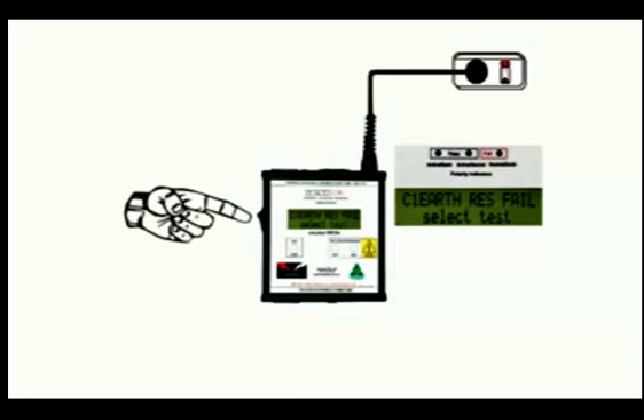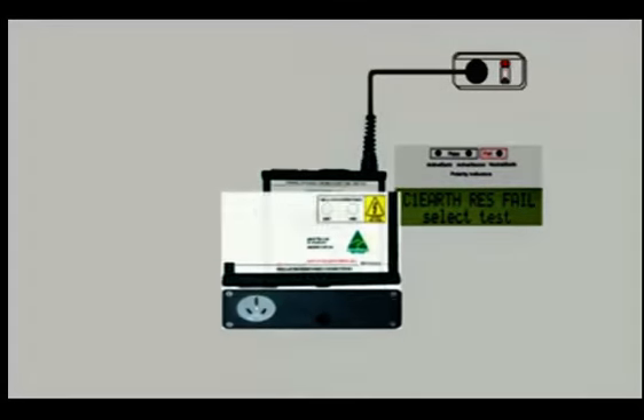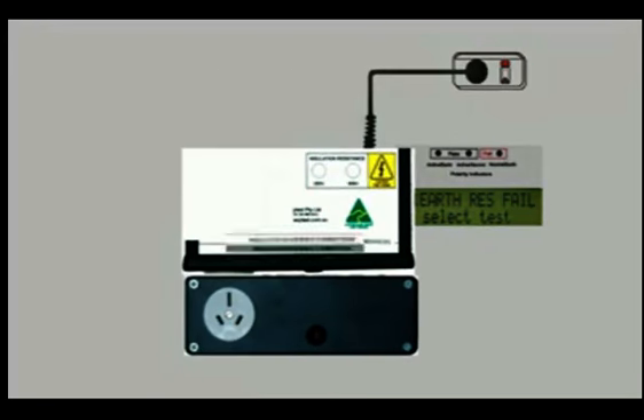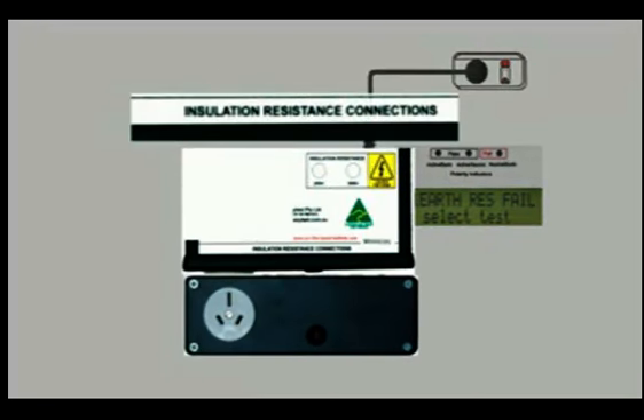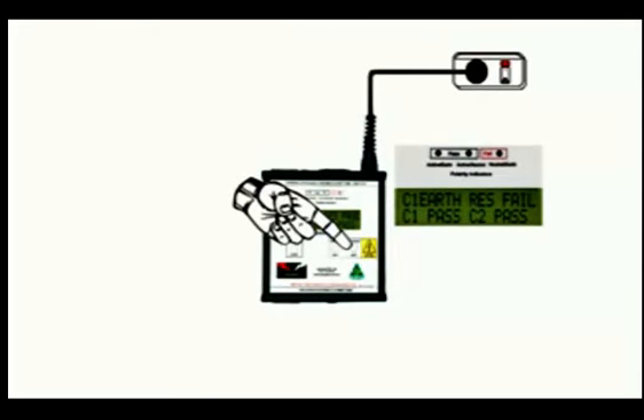Selection is via the rocker switch. In the off position, the Mega can test RCDs by pressing the start button, and, using the connections on the bottom of the Mega, do static appliance tests. Insulation resistance being checked at 250 or 500 volts as selected by these push buttons.